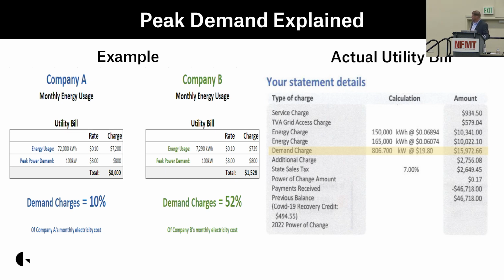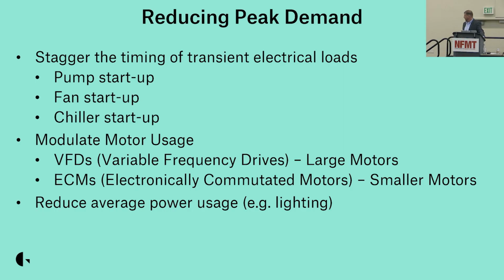Now, if you look to the right, this is an actual utility bill for the facility we're talking about. It's got its kilowatt hours, everything. Right here, we've highlighted what they're paying: $19.80 for kilowatt. Above it, they're paying 0.06 per kilowatt hour. So kilowatt hours is your energy used, your kilowatts is your demand charge. If you look at this bill, the total bill down here is like $46.7 thousand a month. $15.9 thousand is your demand charge. A third of that bill comes from the demand charge. So that energy, we're going to use it. We can try to lower it through lighting retrofits and through other things, but that demand charge, if you can bring that down, that's going to help tremendously.